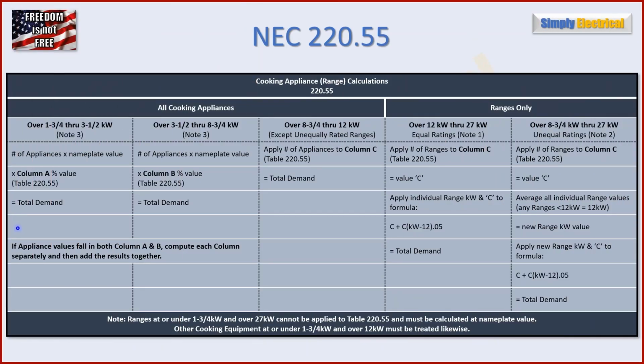Okay, now here is a formula table that I've constructed, and this makes it so simple. You will only need this table and table 220.55 just to reference, and you can do any range calc that comes at you. This makes it so simple because all you have to do is figure out what size range you have. That tells you immediately what column you start with, and once you're in that column, you stay in that column and you get your answer, and it's really simple. These get a little more complex over here, as you can see, but even those are pretty simple.